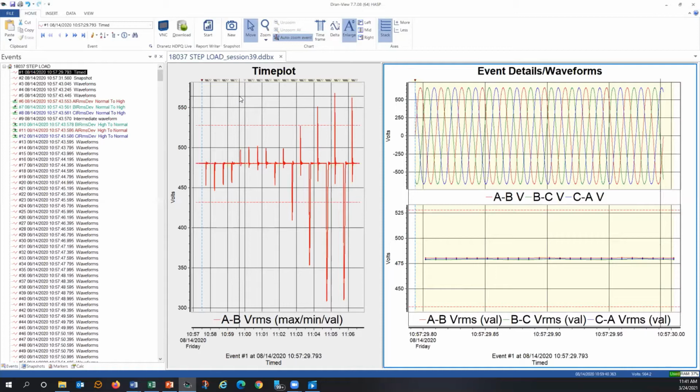So this is a generator test. And in a generator test, it's very important to follow the frequency, the cycle by cycle frequency. So we're going to focus on this application because it's an excellent demonstration of the time plot and harmonics calculator. So it's computing new information for you. It also has the ability, similar to the math package, to recompute data from the instrument if you wish to do that.